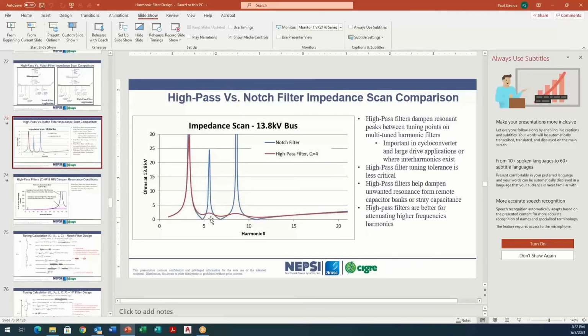When you do harmonic filter design, the general concept is to start at low tuning frequencies and work your way up. The reason being is that you get this resonant point that sits below the tuning frequency. So if you have a single harmonic of concern, and it says greater than the 30th harmonic, you can put in just a single, say, 30th tuned harmonic filter. The issue is you get the resonant point that exists below the tuning point that you need to deal with. So the solution to that is to put in a damped harmonic filter, or a C high pass or high pass filter. It's going to be a high pass filter because of frequency, and you can take care of that violation. But that's how you deal with it with a high pass filter.